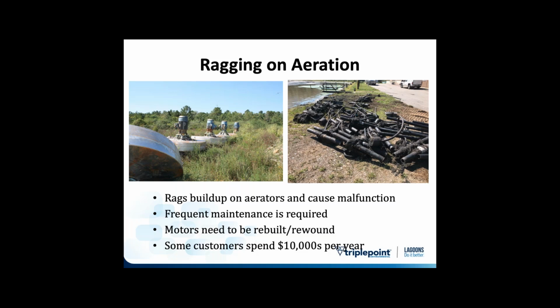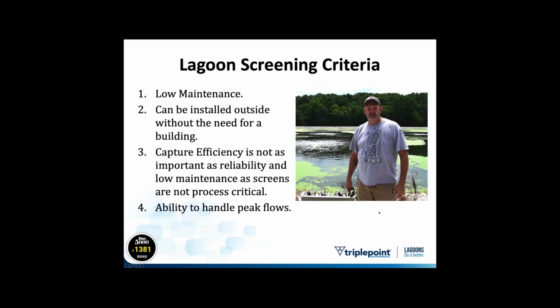This was also something that we saw at Revelstoke when we replaced the system. They dropped like 3 pounds of pressure as soon as they turned our system on, because they just took out all these clogged up aerators, right? So there is a maintenance cost and a maintenance nuisance to it. There's an energy cost to it as well. So that's the big issue.